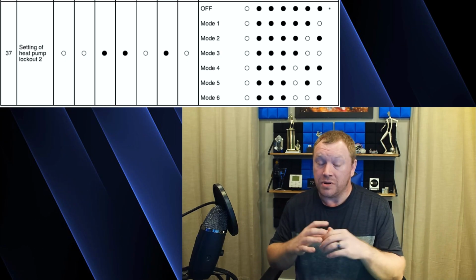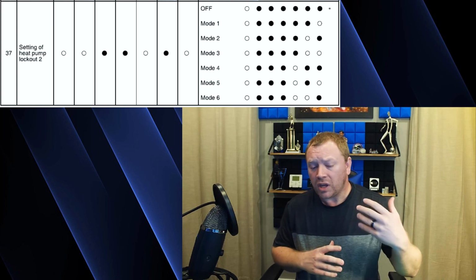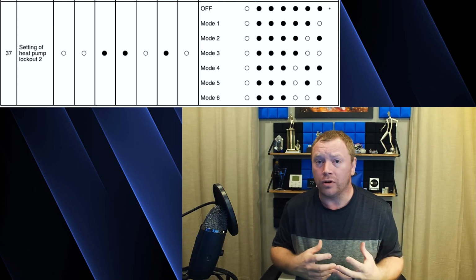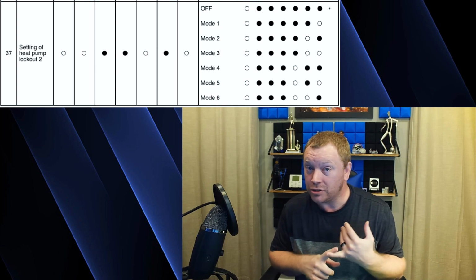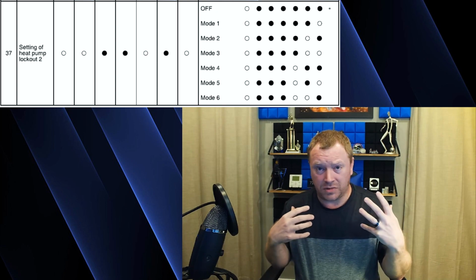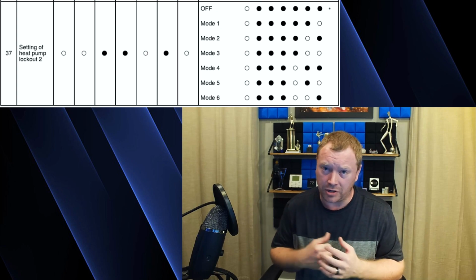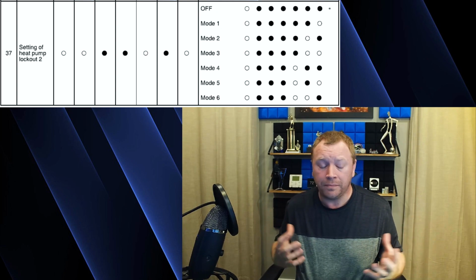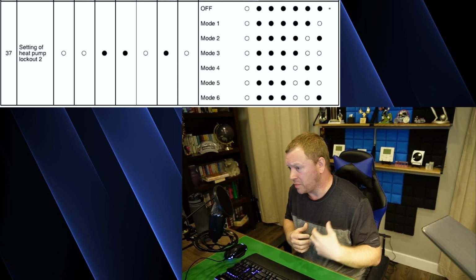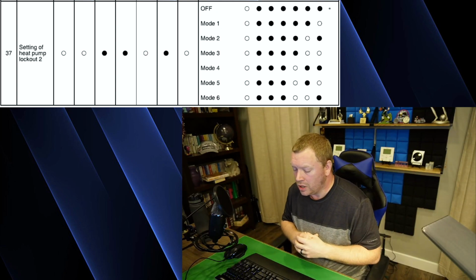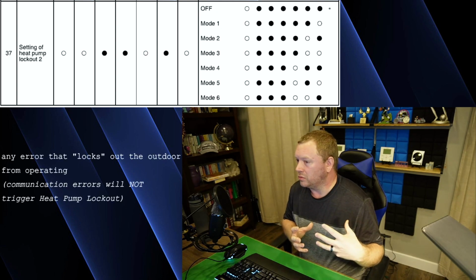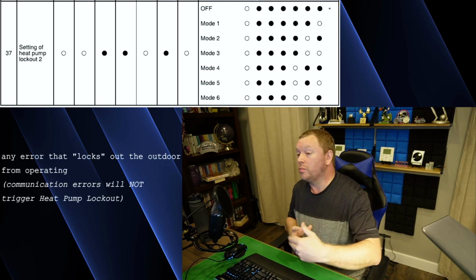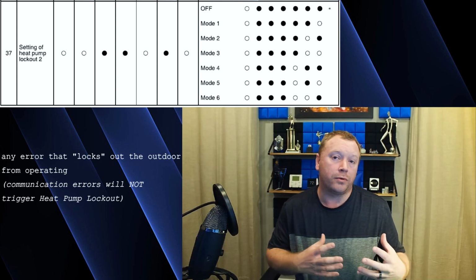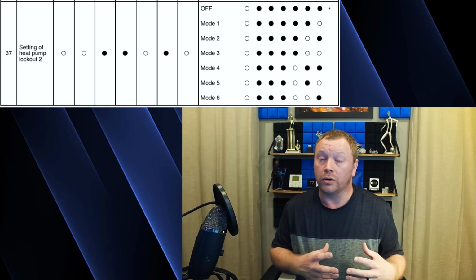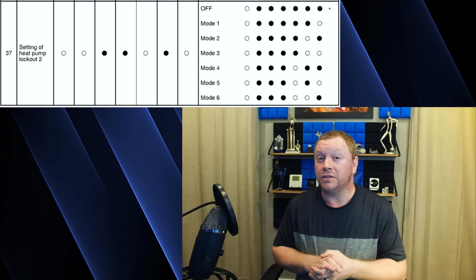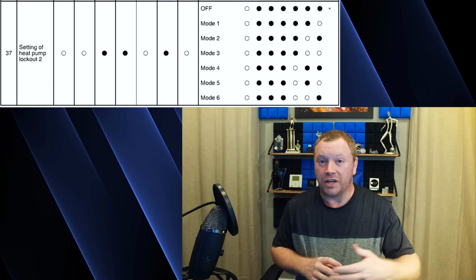So now at any point in time, if the outdoor unit has an error, and you can test this by unplugging one of the pressure transducers if you want. The system doesn't have to be operating. As soon as you unplug that pressure transducer, boom, there's going to be an error code, right? Because now it doesn't see that voltage coming back through that pressure transducer. So once you have any error that will lock out the heat pump from operating, your backup heat source will become the new primary source of heating, and it will follow your thermo on-off deadband field settings that you programmed earlier on in the commissioning process.